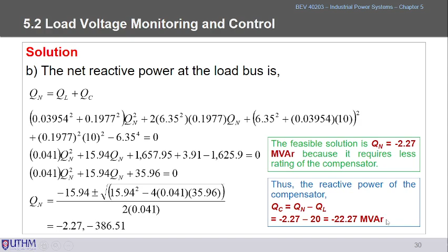Okay, then after we monitor the loads, just now was one of the methods. We compensate the voltage using the injection of Q. For the injection of Q, we have several methods here. The Q can be injected using the excitation control of the generator. That means we control the voltage by injecting the Q at the supply level, the power supply level, the incoming level.